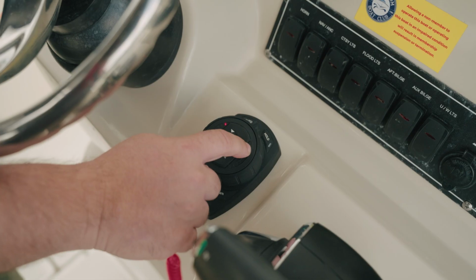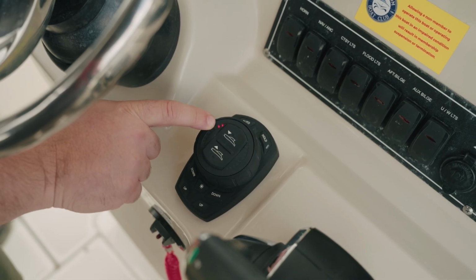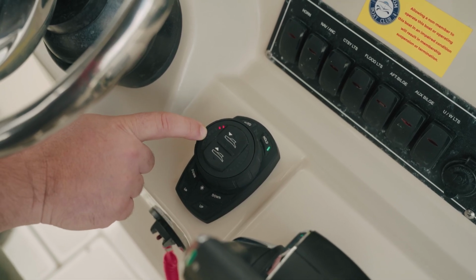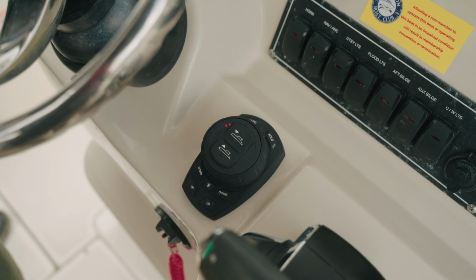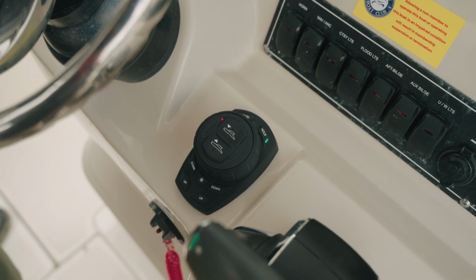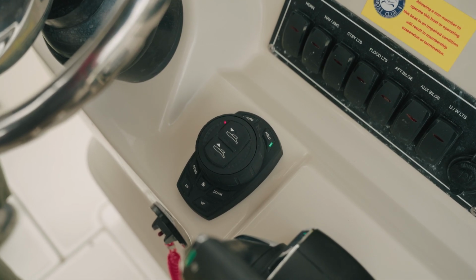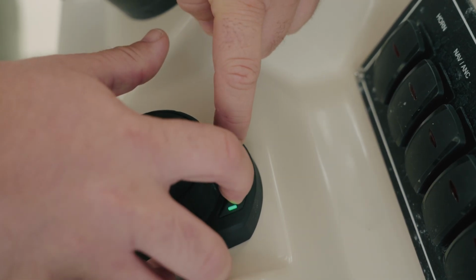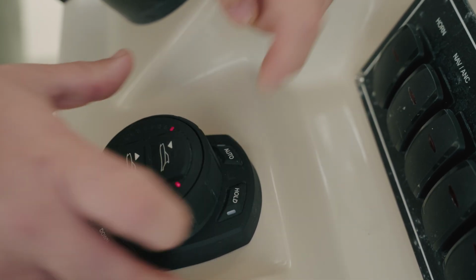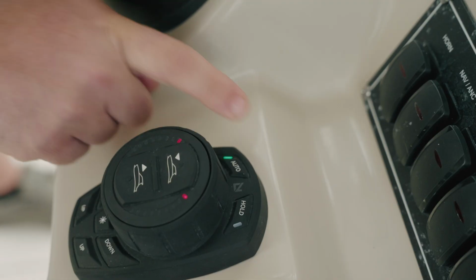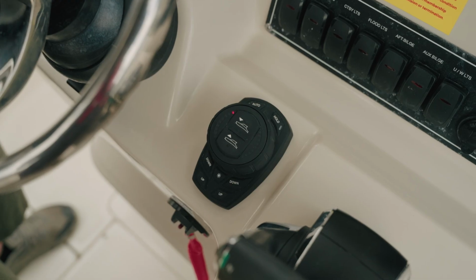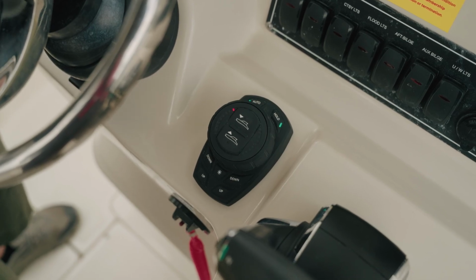When the light is off, you'll notice that two lights go away on the left-hand side. That means that our commissioning at this point is now complete, as we have already set a level roll and we have turned pitch control off. We can do a long press and hold of the auto and hold buttons to exit the menu at this point in time. Today we are going to commission both roll and pitch, so we're going to turn pitch control back on in the system.